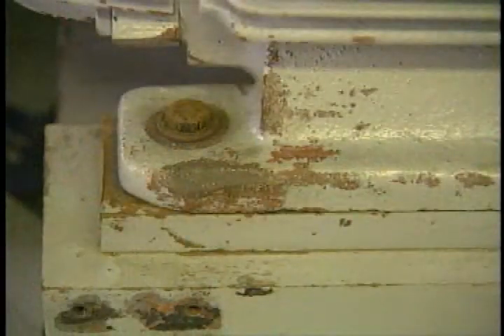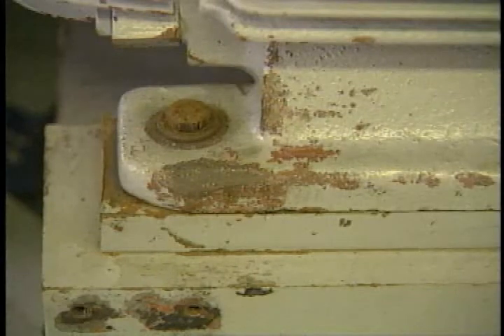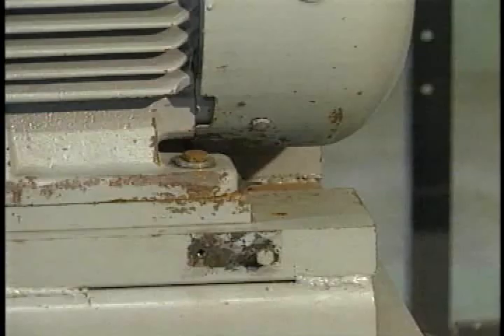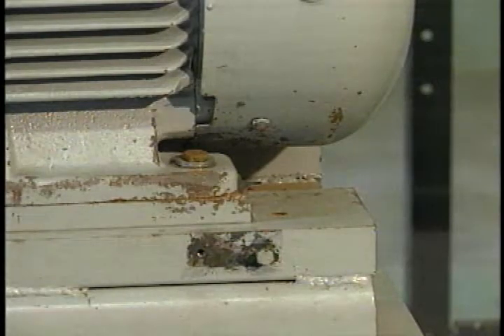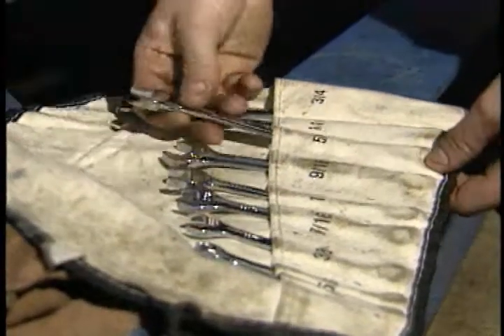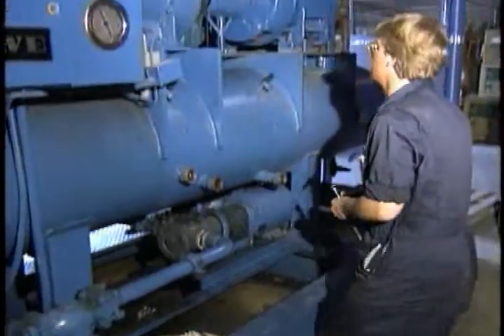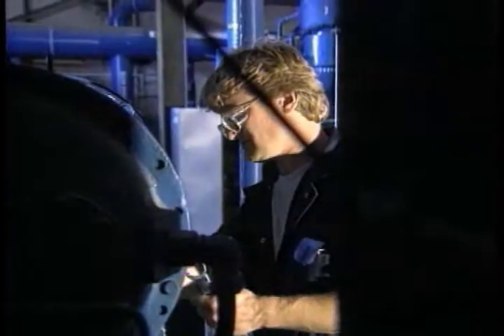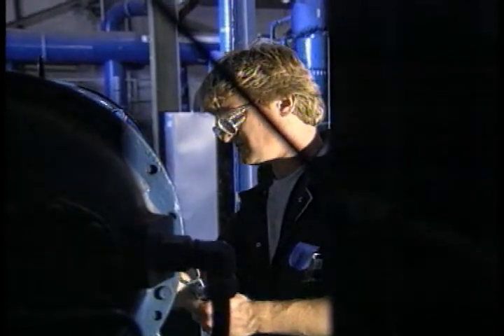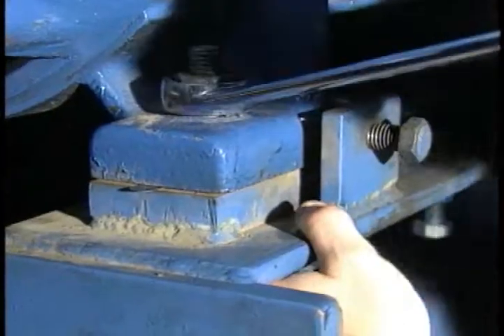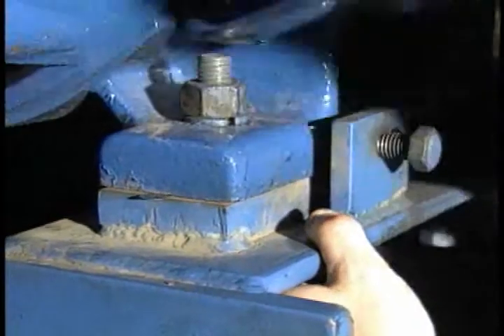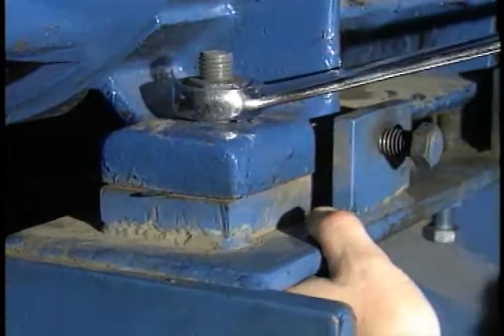The first step in preparing equipment for laser alignment is to check the bases of the units. Make sure you start with a solid foundation and that both units sit perfectly flat. Next, secure the driven unit, in this case, a compressor on an industrial chiller. You will probably have little choice in the placement of the driven unit, so it is leveled and bolted down first. The driver unit is adjusted to it.